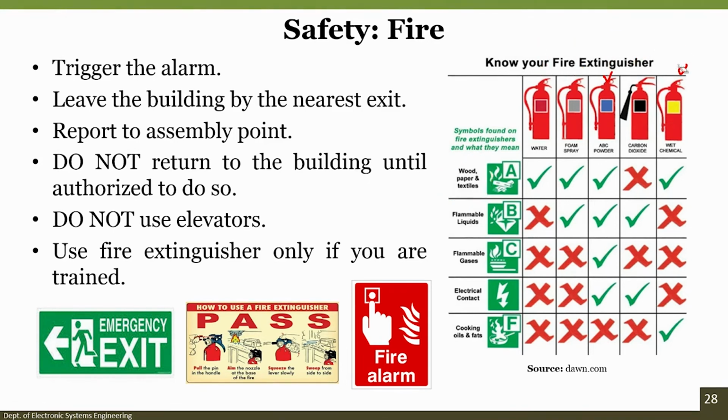Same thing, if I go for the flammable liquids, if flammable liquids catch fire, then I cannot use water, water is not allowed. I can use foam spray, ABC powder, carbon dioxide, and wet chemical is not allowed, right. Same way for flammable gases, electrical safety and cooking oils and fats. So, all things are on the slide, you can easily see, you can go back and look at the lectures and understand how the things are done.